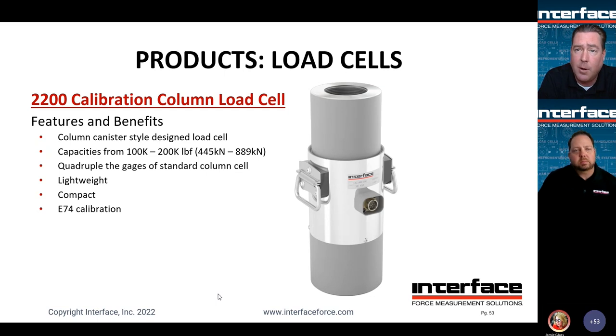We've done a lot of different variants of this load cell as well, so it's not just female to female orientation. We've done custom items. A real common one we did was for, as I referenced earlier, concrete machine testing. We've done some custom variants of this with just a spherically radiused upper surface that provides a very high capacity, very portable calibration grade load cell for that type of testing. So if you're on the road testing that type of machine, that can be a great option for you.